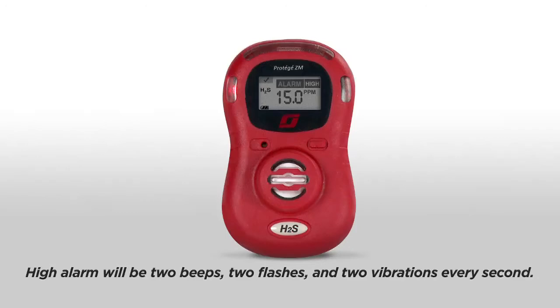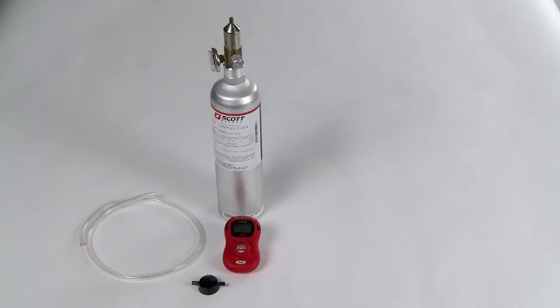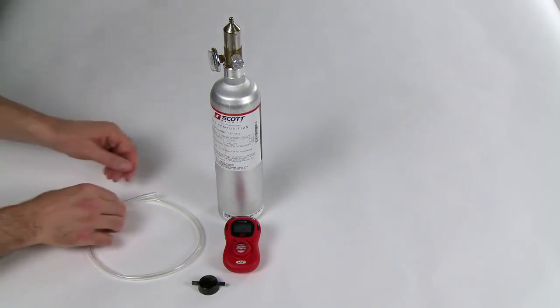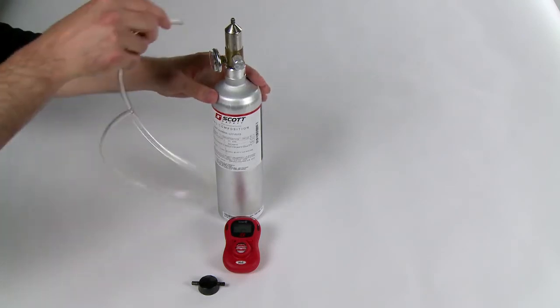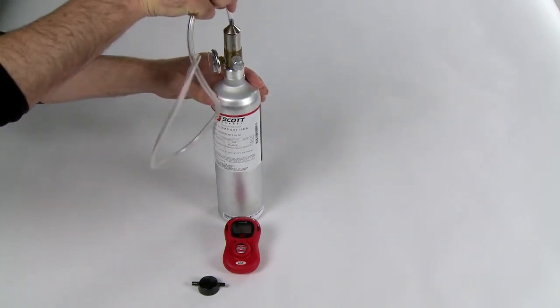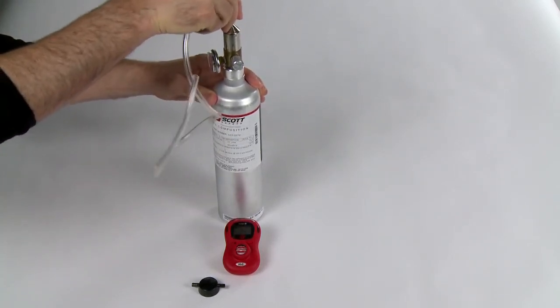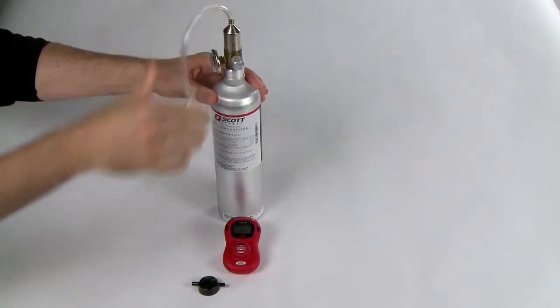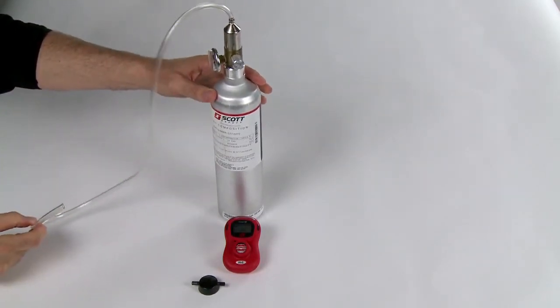Scott Safety recommends performing a bump test in a well-ventilated area prior to each day's use. The purpose of the bump test is to confirm the monitor will react to the target gas and go into alarm. To manually bump test the Protege ZM, use the appropriate calibration target gas that exceeds the low alarm point setting. Use flexible tubing, available from Scott, to connect the calibration gas bottle to the calibration cup.